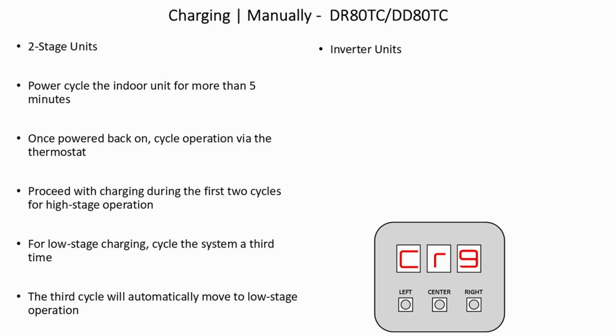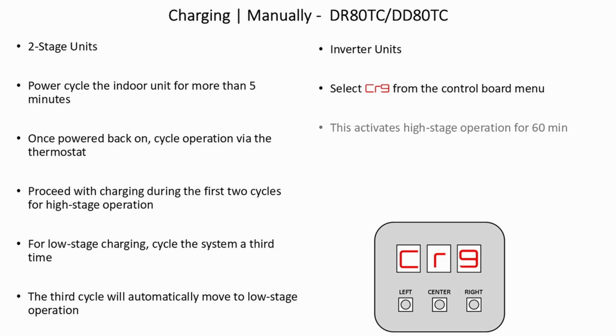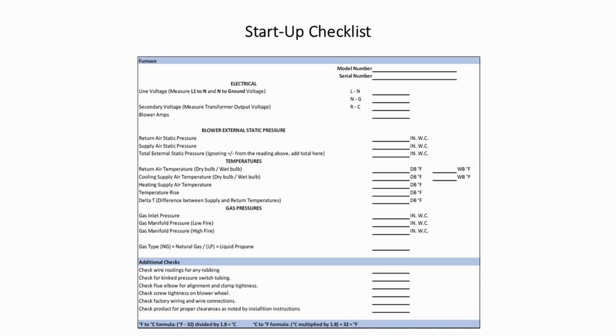For inverter units, select Cr9 from the control board menu. This activates high-stage operation for 60 minutes. It may be manually disengaged, and it automatically exits after 60 minutes. Here is a startup checklist for the furnace. Please start by adding the unit model number and serial number.